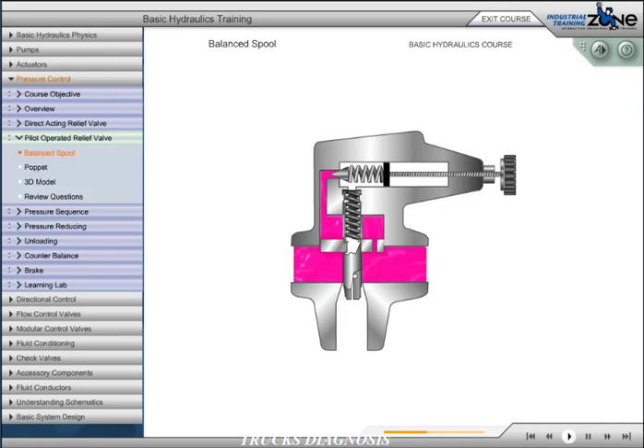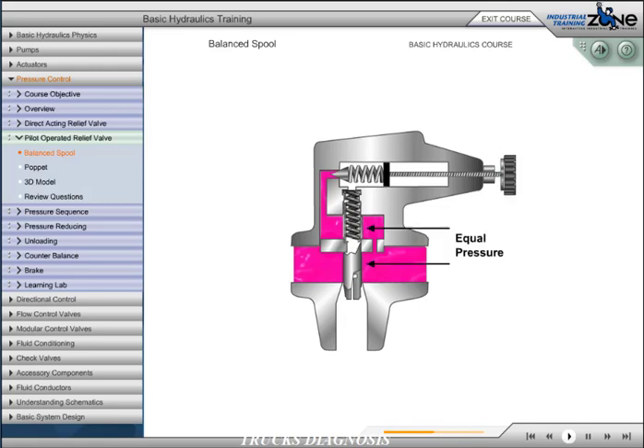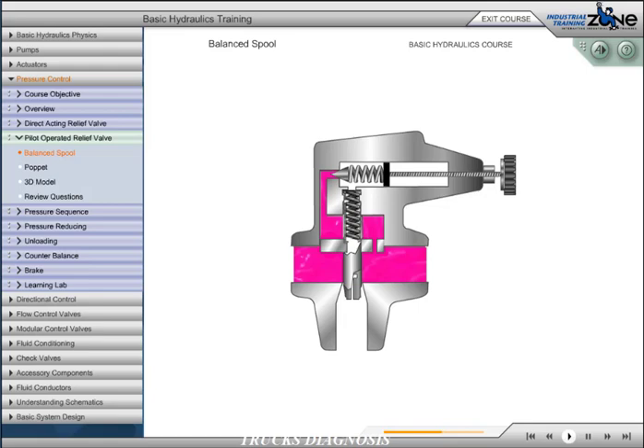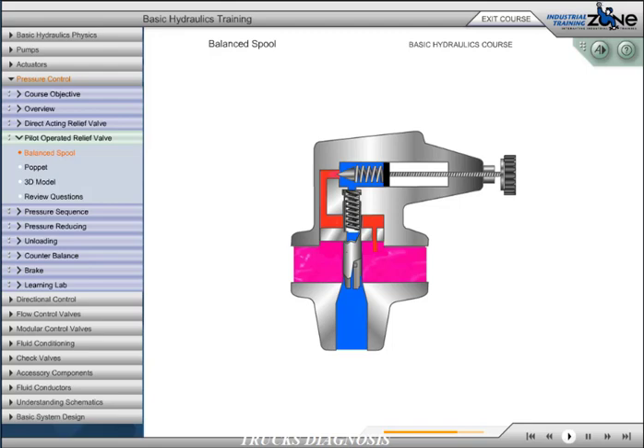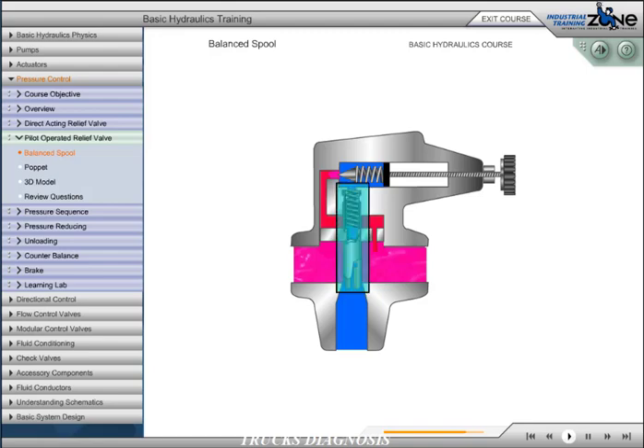Relieving action through the main spool is as follows. As long as system pressure is less than relieving pressure set on the control knob, pressure in the main spring chamber is the same as pump line pressure because there is no flow through the control orifice. When pump line pressure rises higher than the adjustment, the pilot relief poppet moves off its seat. This starts oil flow from the pump line through the orifice, across the pilot relief poppet, and to the tank. This restricted flow creates a pressure difference. This pressure imbalance causes the main poppet to move off its seat, discharging enough pump flow to prevent any further rise in pump line pressure. When pump line pressure drops below the control setting, the pilot relief closes, flow through the orifice ceases, and the main spring reseats the main poppet.